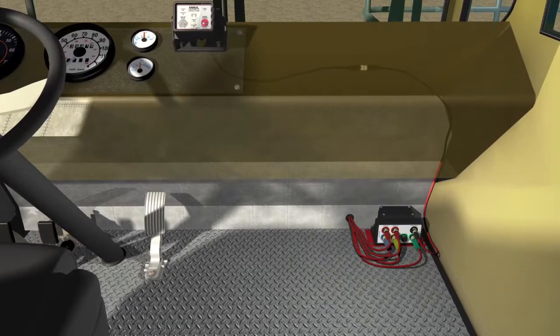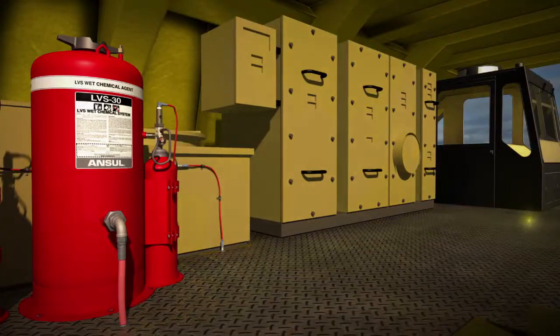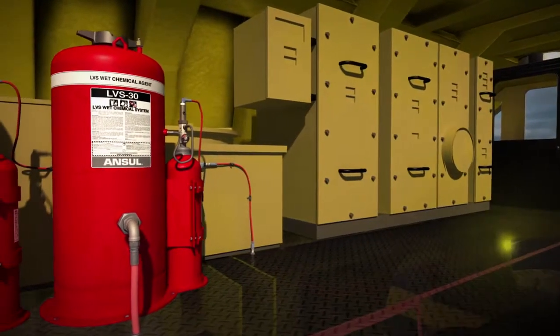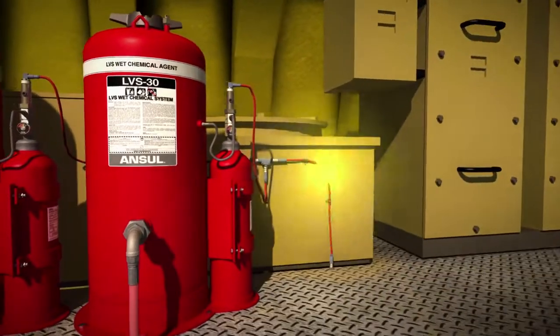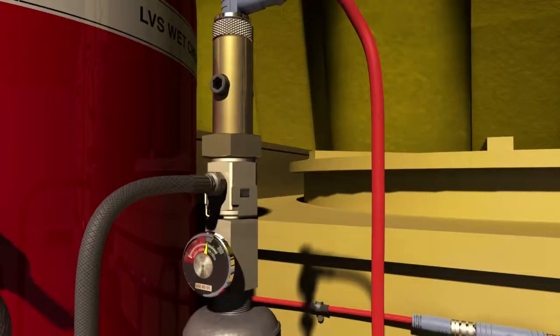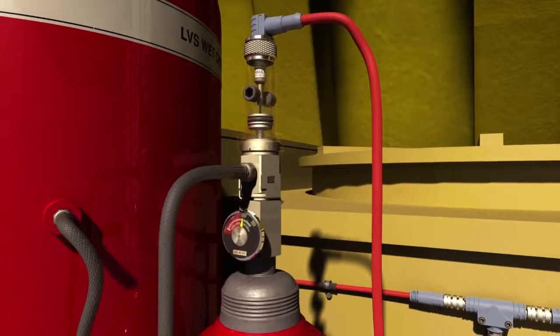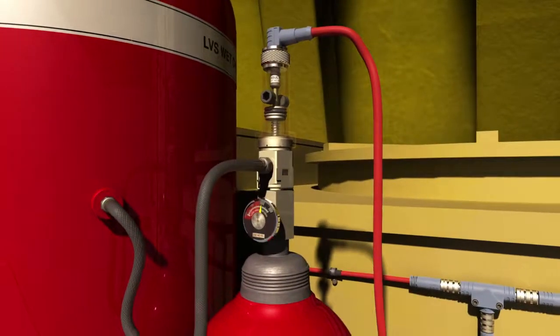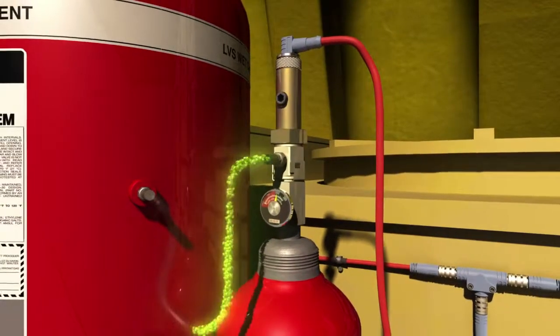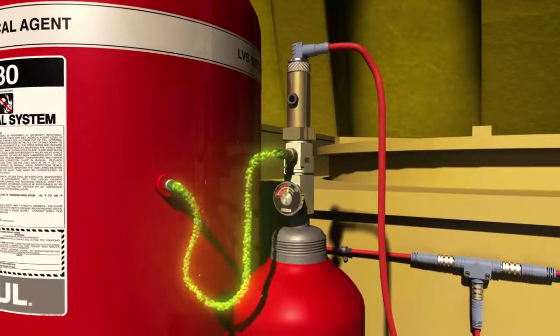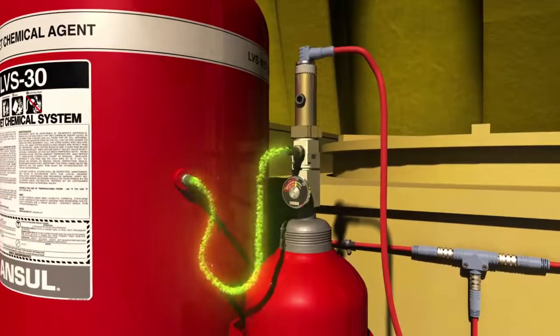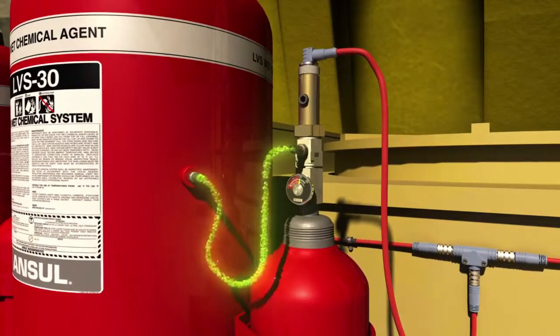After the predetermined time delay period, the CheckFire 210 interface control module sends a signal to the pyrotechnic actuation device. The protracting actuation device generates force to drive the electric pneumatic actuator puncture pin through a seal in the expellent gas cartridge, allowing the nitrogen expellent gas to flow into the agent tank.